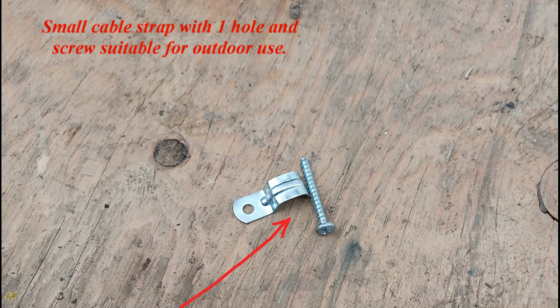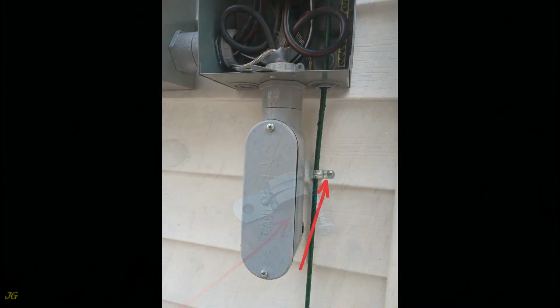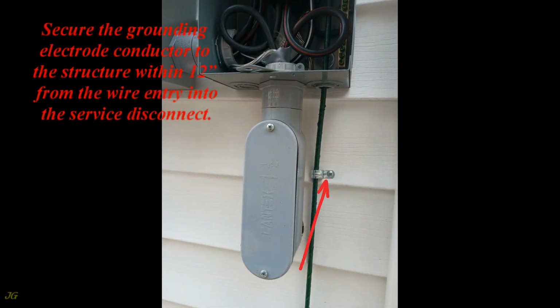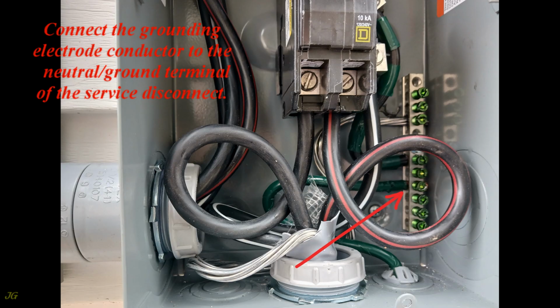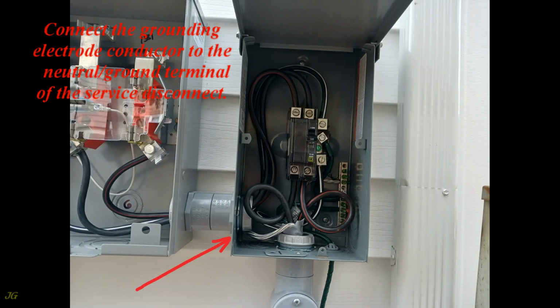Small cable strap with one hole and screw suitable for outdoor use. Secure the grounding electrode conductor to the structure within 12 inches from the wire entry into the service disconnect. Connect the grounding electrode conductor to the neutral, ground terminal of the service disconnect.